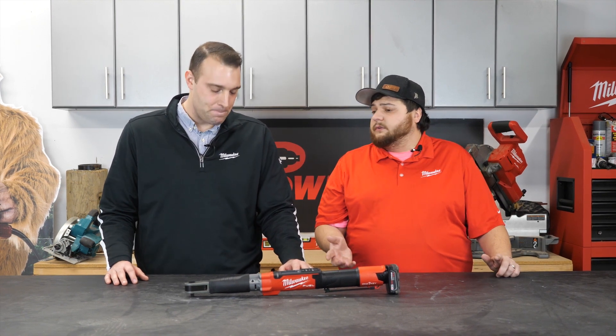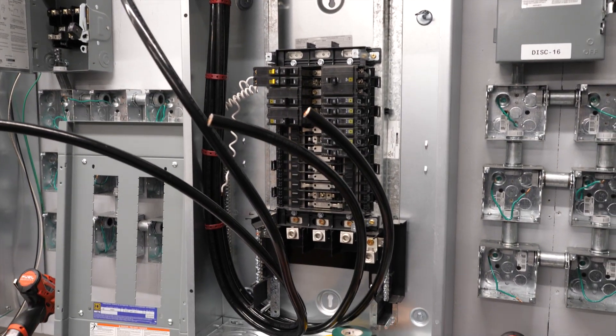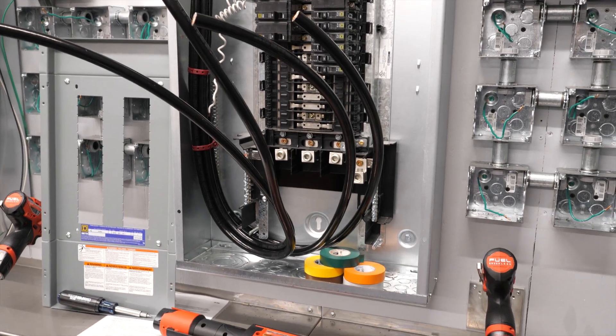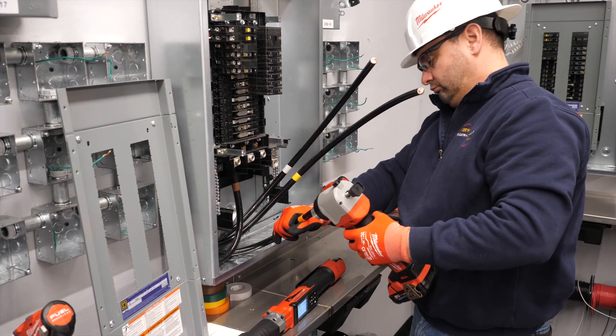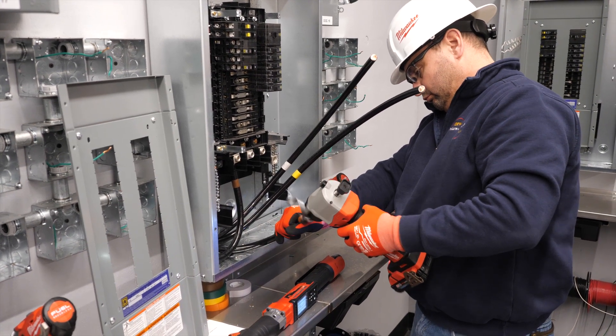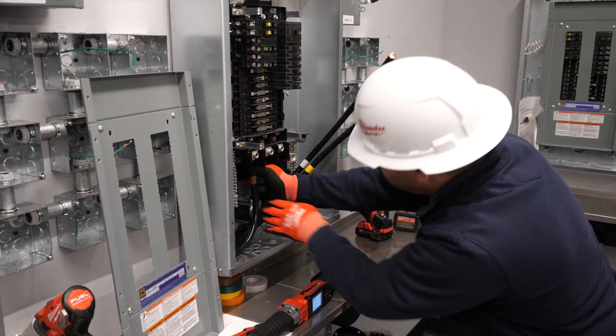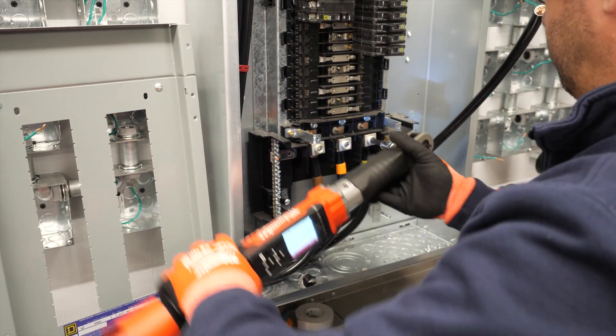Joe and Jay took this over to the Electrical Trades Center next door. He really brought this thing to life — he showed us two real-world applications, starting from the ground up: measuring the MCM cable, stripping it, and measuring all the way into the junction box where we really saw this thing in use, fastening it up to that green light at 275 inch pounds.